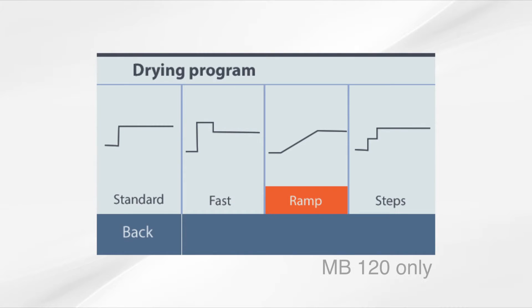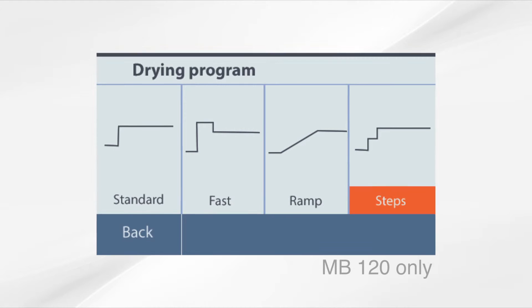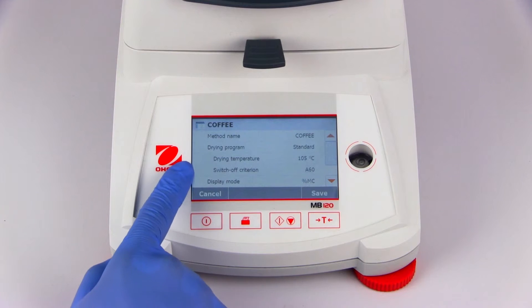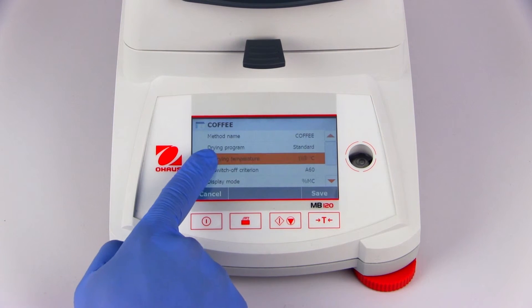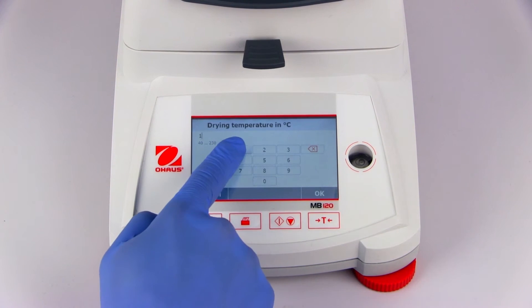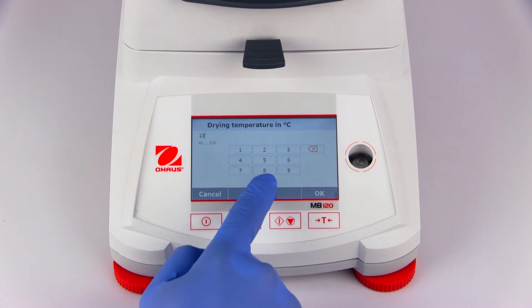The Ramp Drying Profile lets you heat your sample to the target temperature slowly over time. The Step Drying Profile lets you set multiple target temperatures and a shutoff criterion for each step. In addition to a drying profile, a drying temperature must be set.